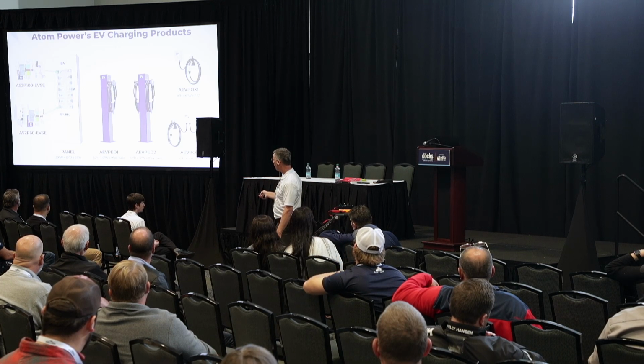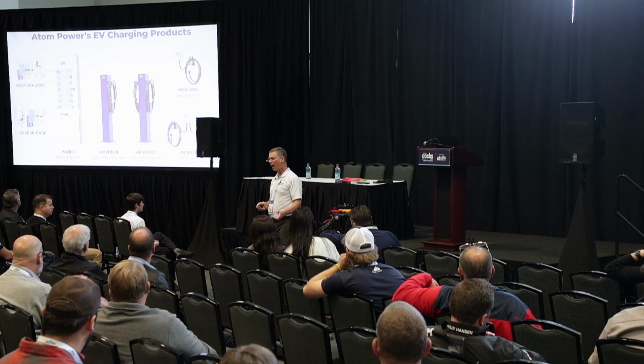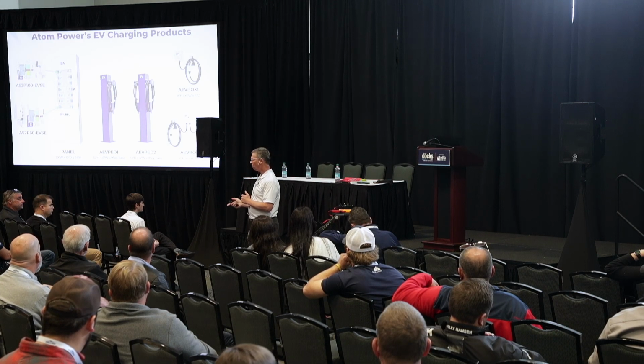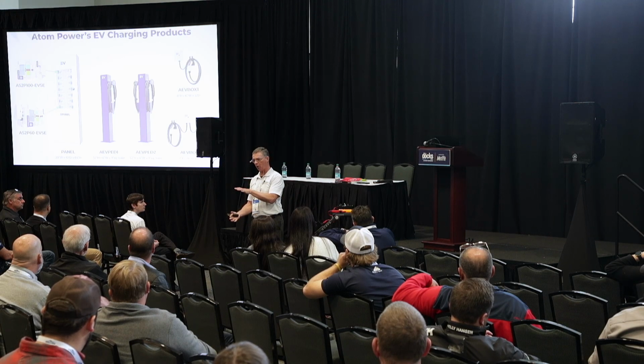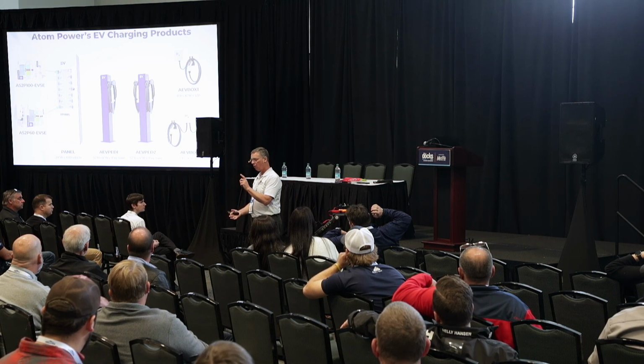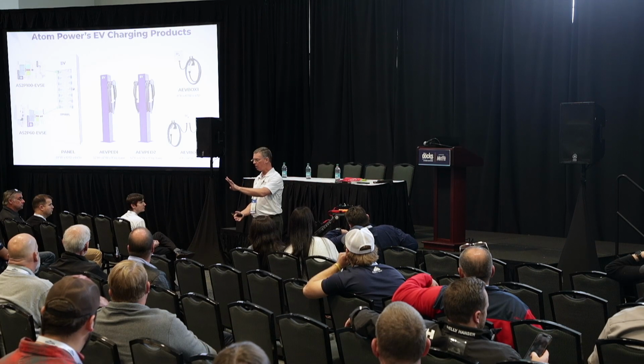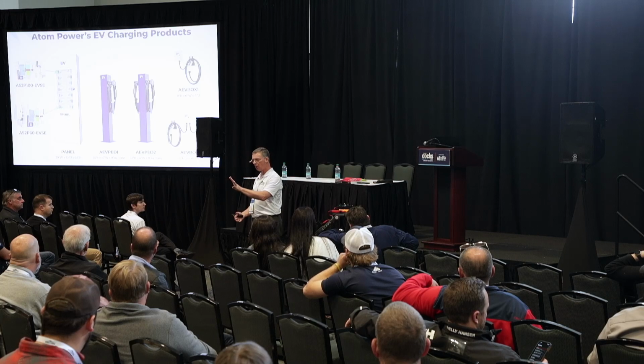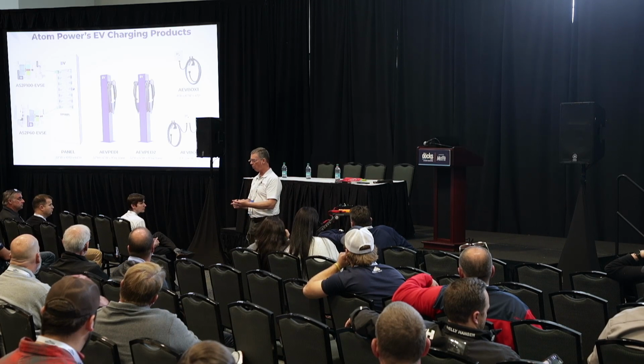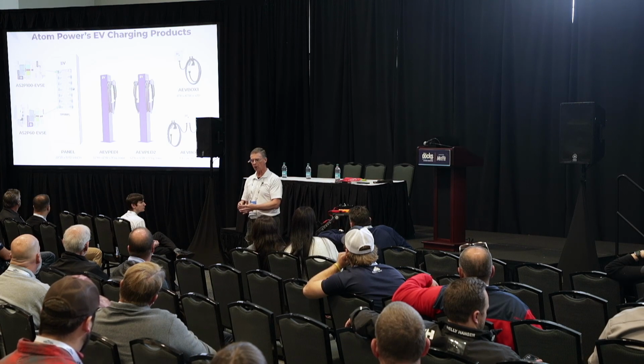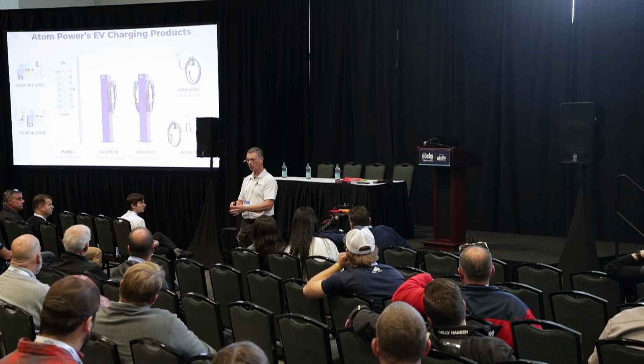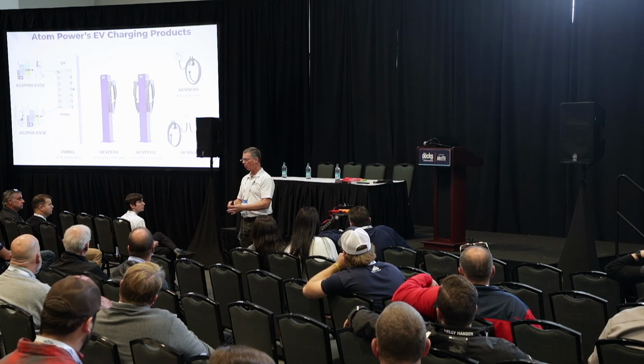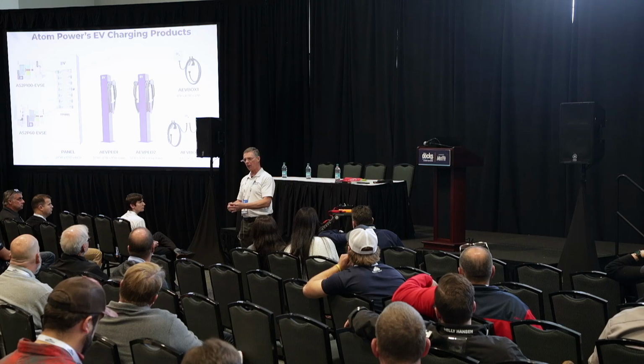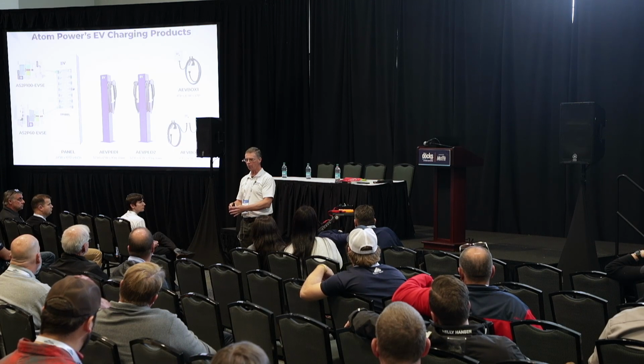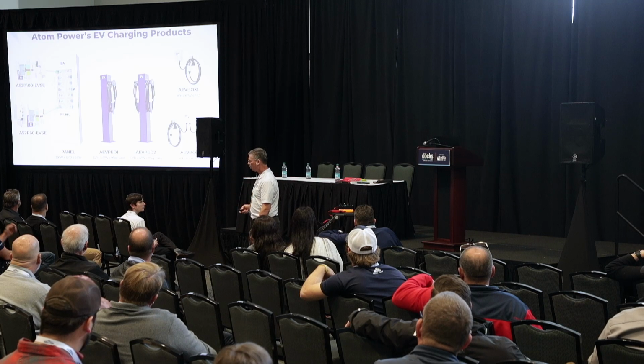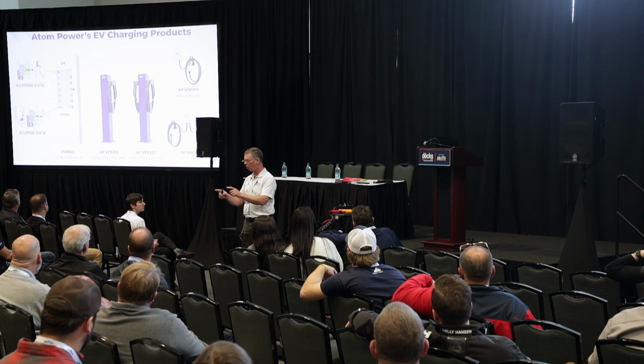But you can connect up to 12 100-amp breakers to this and supply 1,200 amps worth of load, and it distributes the 400 amps evenly if you want, or you can set priorities. You can have 4 boats or 3 boats, whatever it may be, that get the 400 amps. Say you're charging boats — you can have priority 1 boats, priority 2 boats, or priority 3 boats. When a priority 1 boat comes in, because he pays more, he gets as much power as he wants out of that 400 amps. Then when a priority 2 boat comes in, he doesn't get any power until the priority 1 boat finishes charging. You can program these solid state controls to manage that power coming in and which circuit it actually goes out to.